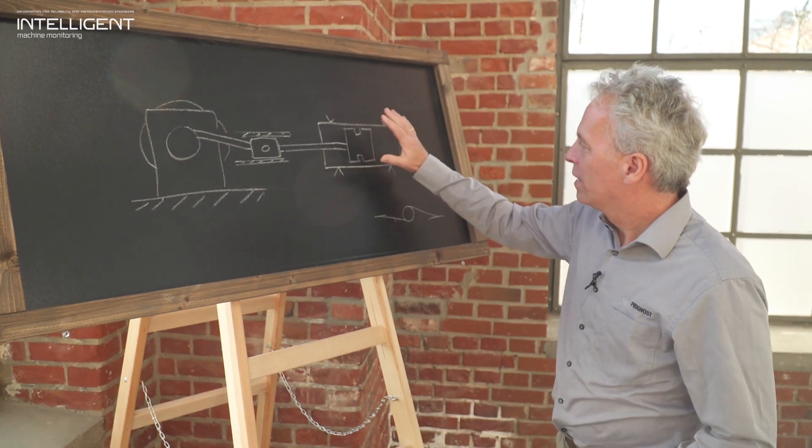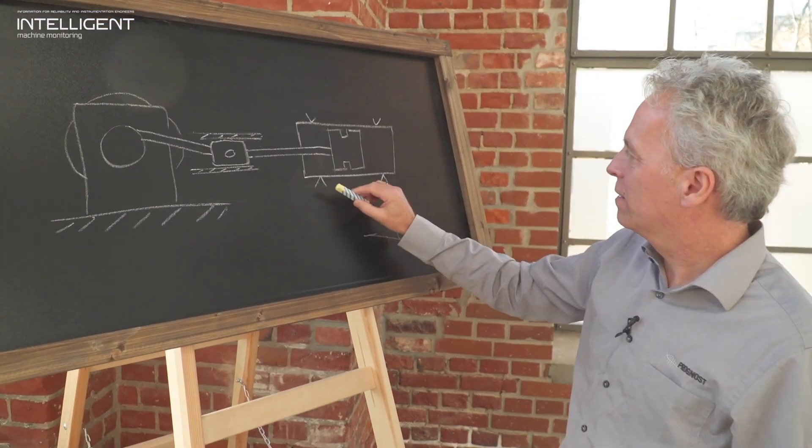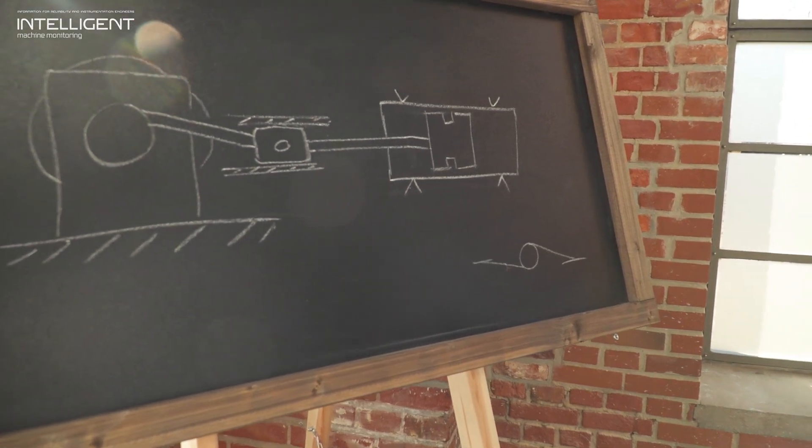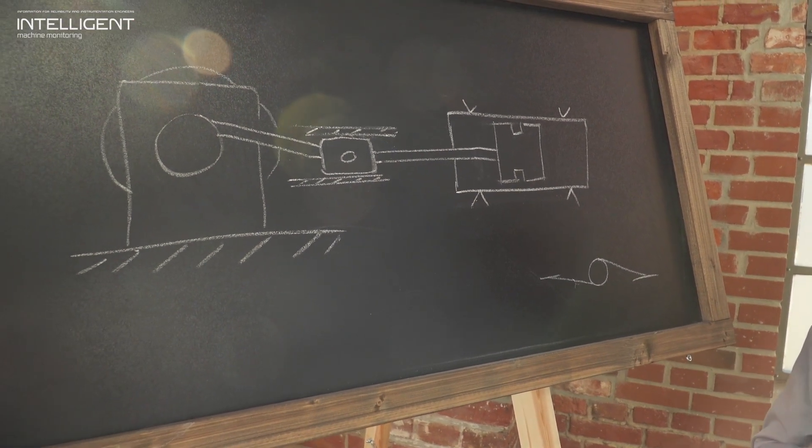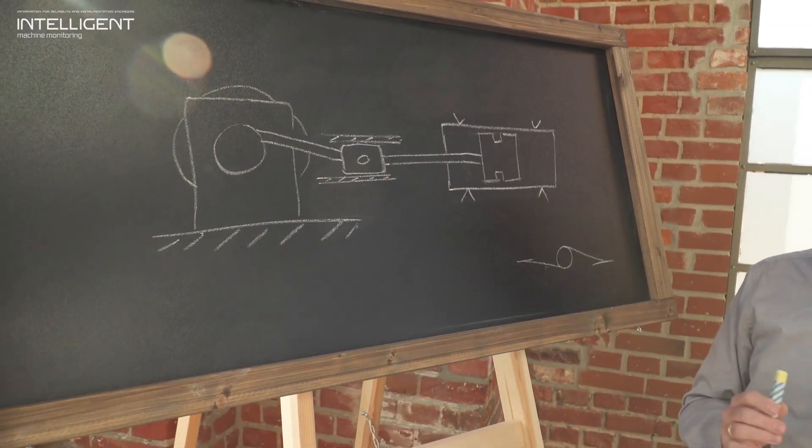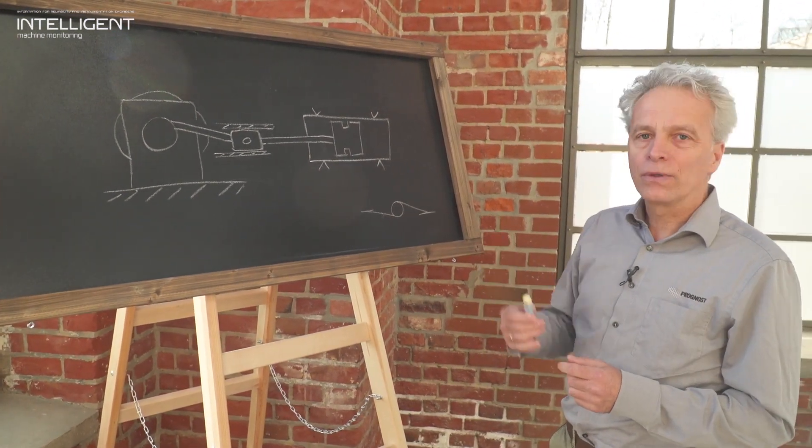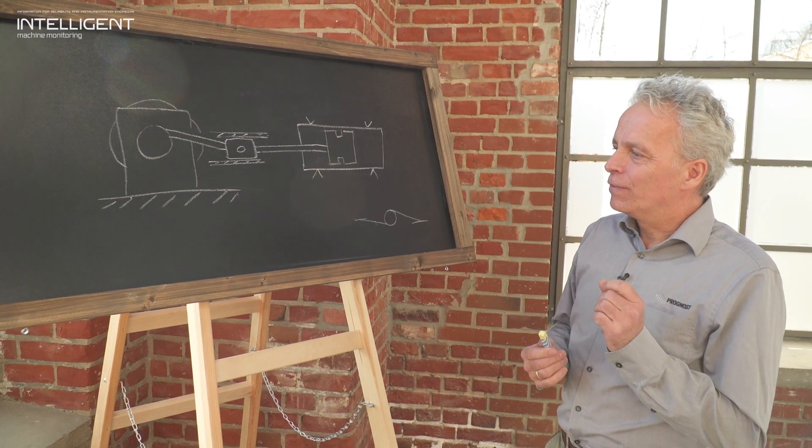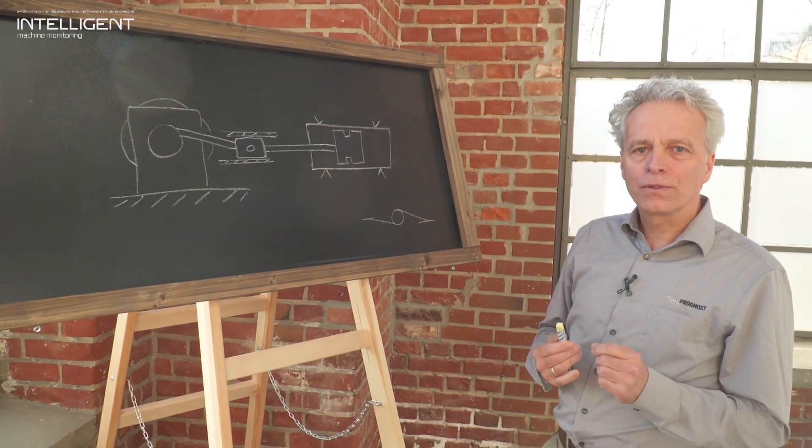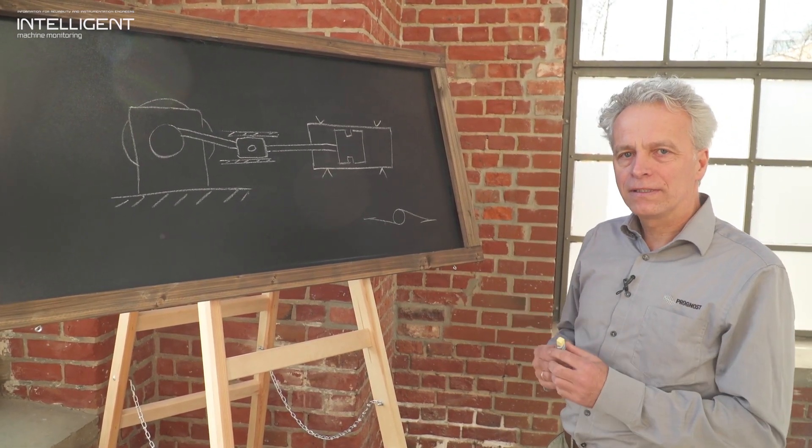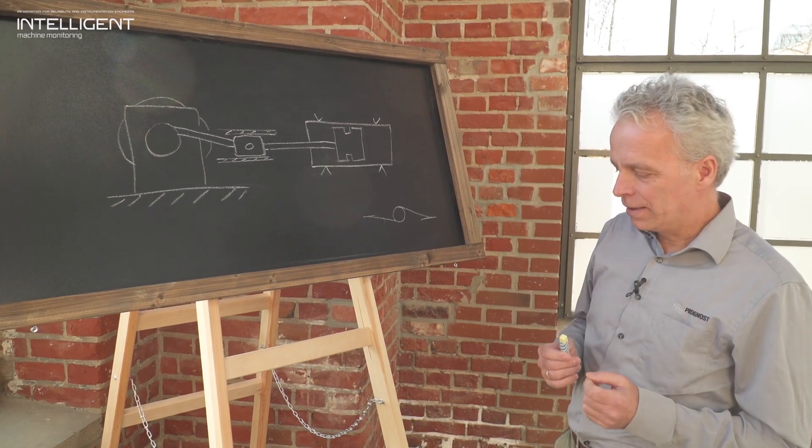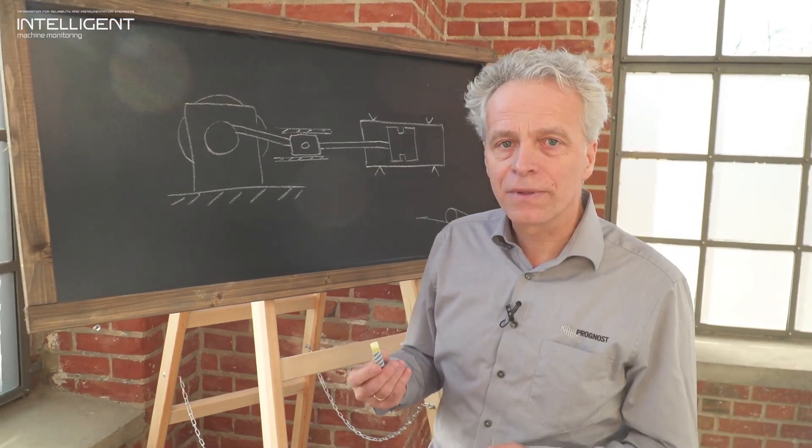Here we have the cylinder with the suction valves and the discharge valves. Now to monitor all the online signals, the dynamic online signals of the sensors that we're going to explain now, we need to reference them to the top dead center of the cylinder. To obtain this, we install a trigger mark at the flywheel and here a trigger sensor which is then installed at the support.